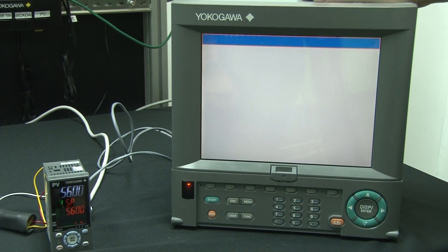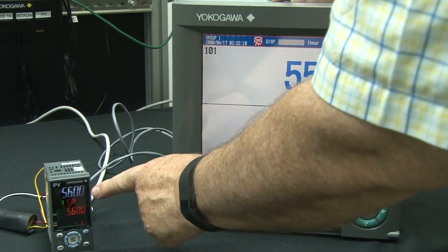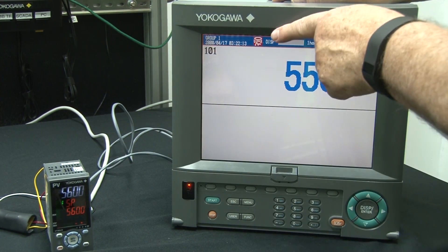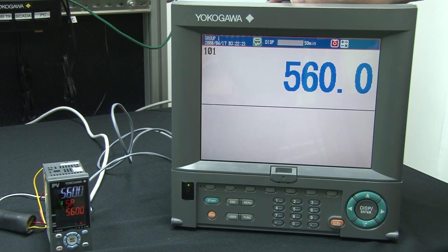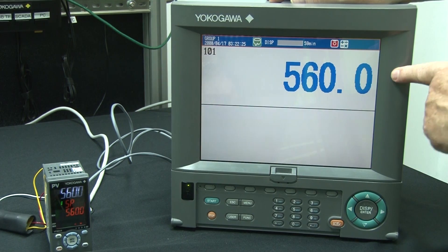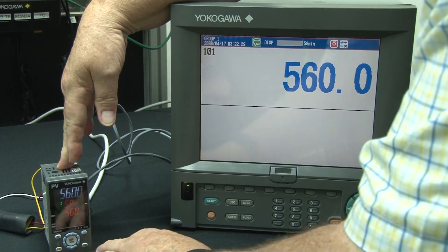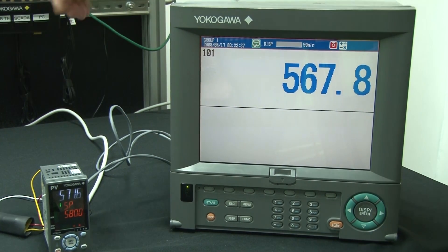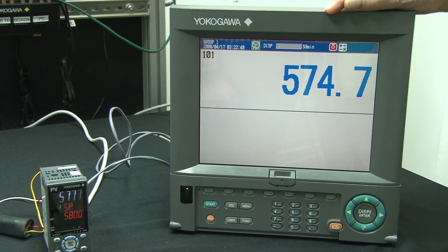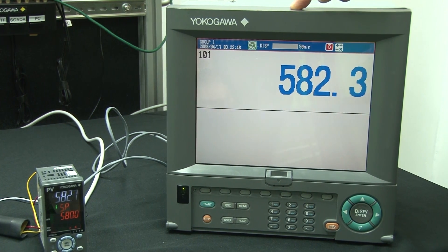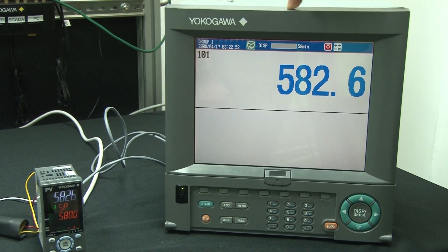Now let's go back and look at the live values. The recorder has to restart when you exit that menu. We can see it's reading 550 but the controller is showing 560; the red mark at the top means the recorder wasn't actually running because we had to stop it when we went into basic setting mode. We start the recorder back again and now it's reading a live value. If we change the set point, we'll see the value on the top line changing and the recorder following along, with a little bit of a delay because the recorder is only reading once a second.